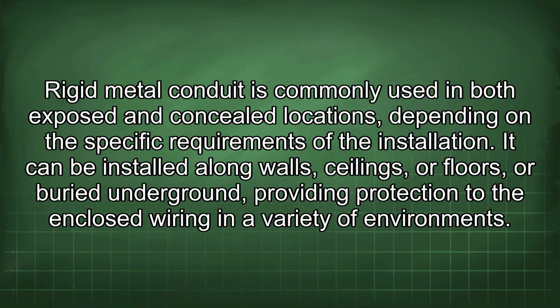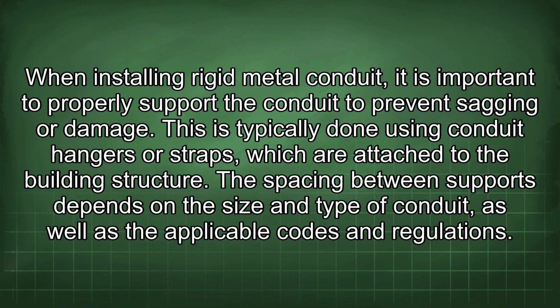Rigid metal conduit is commonly used in both exposed and concealed locations, depending on the specific requirements of the installation. It can be installed along walls, ceilings, or floors, or buried underground, providing protection to the enclosed wiring in a variety of environments. When installing rigid metal conduit, it is important to properly support the conduit to prevent sagging or damage. This is typically done using conduit hangers or straps, which are attached to the building structure. The spacing between supports depends on the size and type of conduit, as well as the applicable codes and regulations.